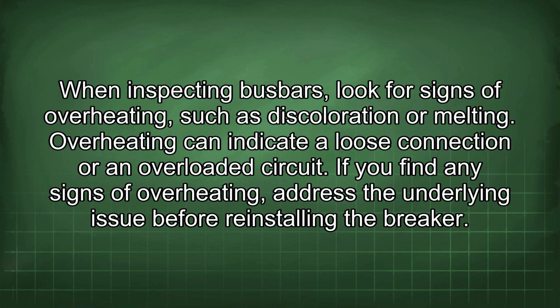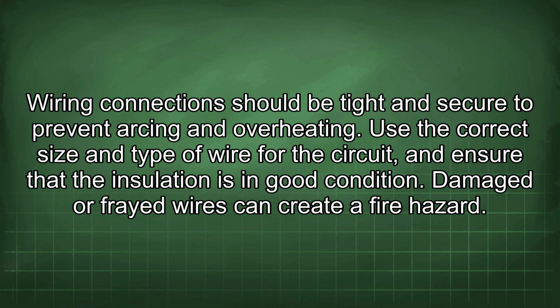When inspecting bus bars, look for signs of overheating, such as discoloration or melting. Overheating can indicate a loose connection or an overloaded circuit. If you find any signs of overheating, address the underlying issue before reinstalling the breaker. Wiring connections should be tight and secure to prevent arcing and overheating. Use the correct size and type of wire for the circuit and ensure that the insulation is in good condition. Damaged or frayed wires can create a fire hazard.